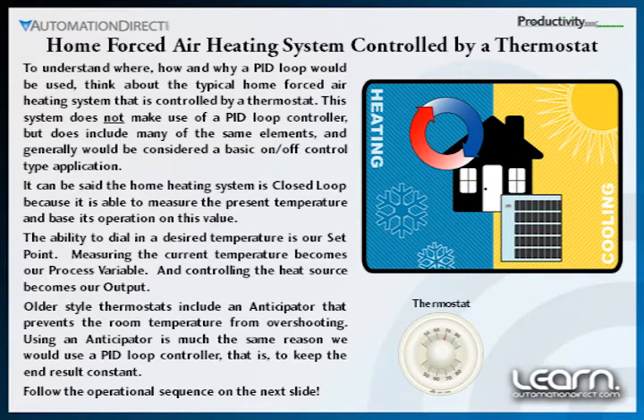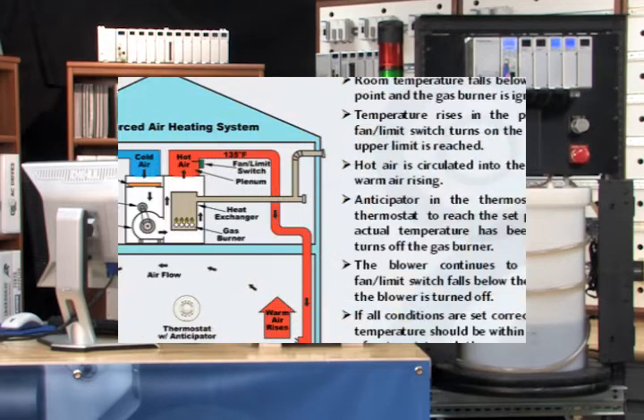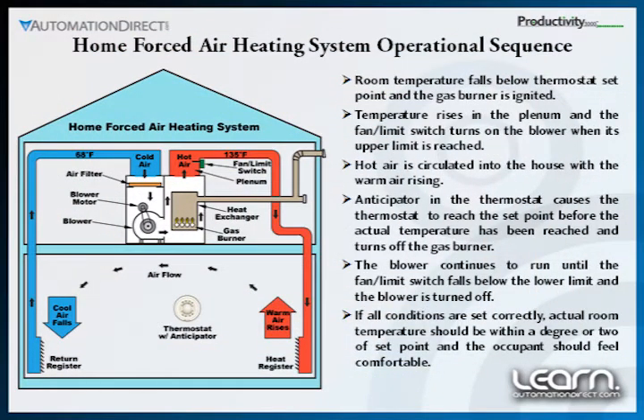When the monitored temperature falls below the desired temperature by a predetermined amount, the thermostat sends a signal to the furnace's burner to tell it to turn on and produce heat for the house. Once the desired temperature is reached, the thermostat turns the heating source off and waits for the next cycle. The heat source in our example is either fully on or fully off, whereas the output from a PID loop controller is varied from no output to fully on to anywhere in between, which allows better control of the end result. The PID's output at any given instance is based on continuously updated calculations within the PID loop instruction. The thermostat, with the ability to monitor the house temperature and determine when to signal for heat, is acting as an on-off controller in a closed loop system.